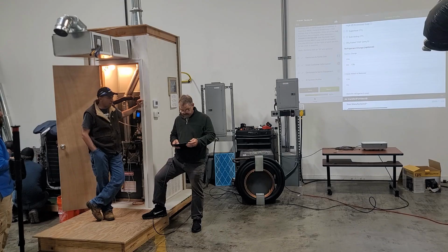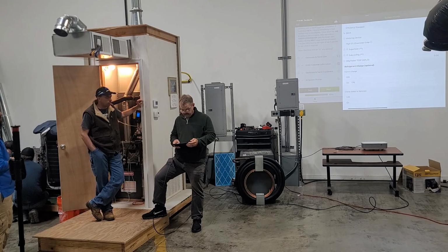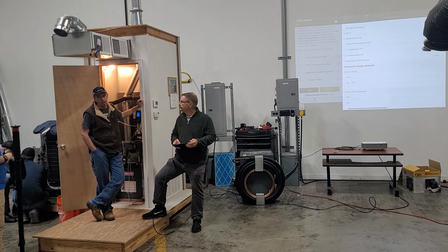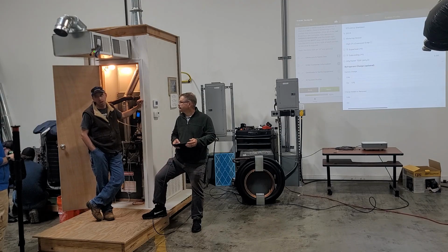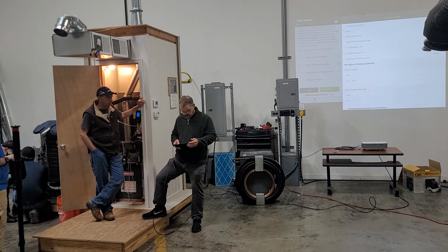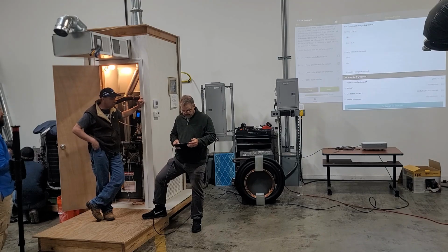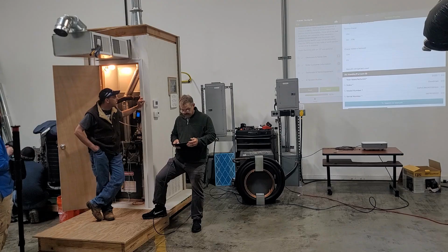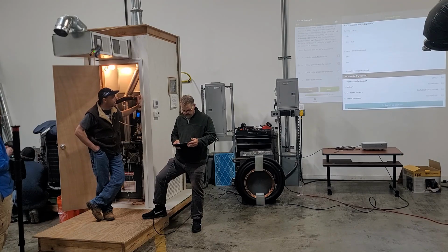High efficiency evaporator, that is an advanced target that I have turned on, that's not on by default, you normally wouldn't see that. What that does is it compensates your suction pressure target for having an oversized evaporator coil, but it only compensates for a half ton step up. If you're working on one of those crazy high efficiencies with, you know, the 5-ton evap, 1-ton condenser, it's not going to be able to compensate for that. It's only a half-ton step difference. Refrigerant charge, that's optional, as it says. You don't have to put it in there, it's just for documentation.